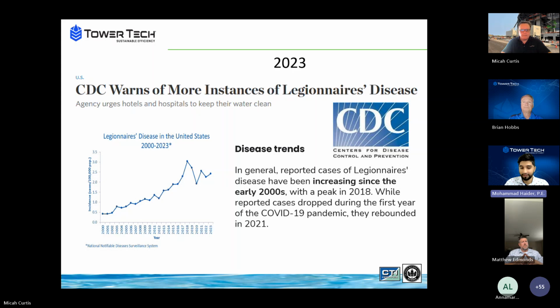And, real quickly, it is unintentional, and despite better awareness and updated cooling tower designs, we still see outbreaks because the problems are more in operational systems rather than purely design based, right? And in my experience, especially with my history with cooling towers, and actually being an owner and operator, cooling towers are typically not considered a direct source of revenue. Because of that, they're not very high on the list when it comes to maintenance schedules and preventive maintenance. So cooling towers are genuinely under-maintained, they're not cleaned, and they're typically run way past their life cycles. These factors all end up contributing to Legionella growth.